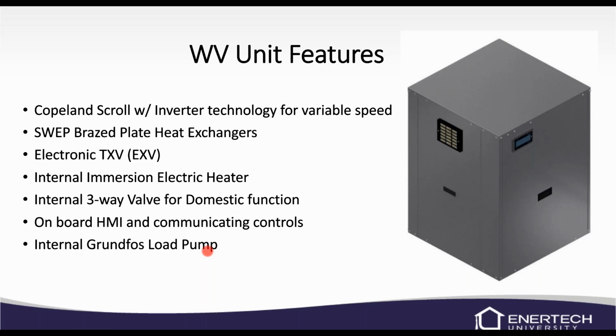So this is the WV to the right. You can see a little box. The 040 and the 060 are the same size, so they're not going to come in a different size cabinet. They'll both be the same size. It's got the Copeland scroll with the inverter technology for the variable speed. We're using two brazed plate heat exchangers in the unit, one for load, one for source. We have an electronic expansion valve. We have to use the electronic expansion valve as we have to throttle that refrigerant pretty quickly.